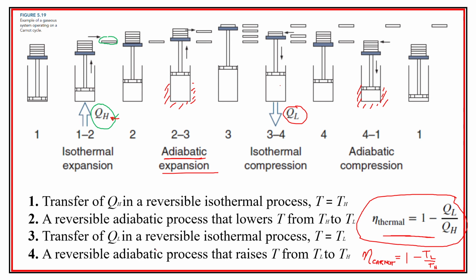And that becomes the maximum amount of efficiency that we can get out of these two temperatures. For instance, this is the temperature that we could get out of the boiler, and this is the temperature that we are dropping it to in the condenser, and we couldn't get any more heat into it from here, so we couldn't get any higher temperature. This is the limit of the temperature that we could bring the steam to, and this is the limit of the temperature that we could bring the condensate down to. So that's what stops us from getting any better efficiency than what is provided.